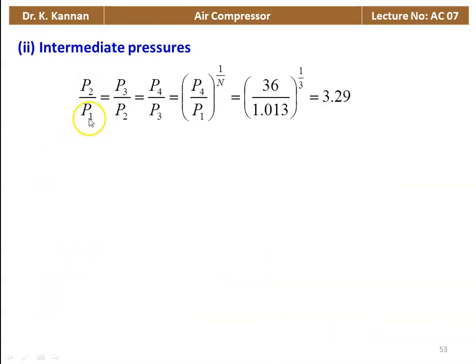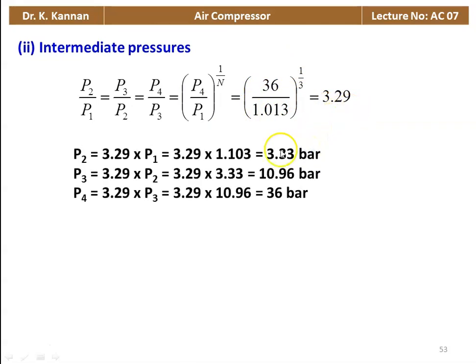For intermediate pressures, equal pressure ratio per stage: P2/P1 = P3/P2 = P4/P3 = (P4/P1)^(1/3) = (36/1.013)^(1/3) = 3.29. So P2 = 3.29 × 1.013 = 3.33 bar; P3 = 3.29 × 3.33 = 10.96 bar; P4 = 3.29 × 10.96 = 36 bar. Pressure at end of first stage = 3.33 bar, second stage = 10.96 bar, third stage = 36 bar.